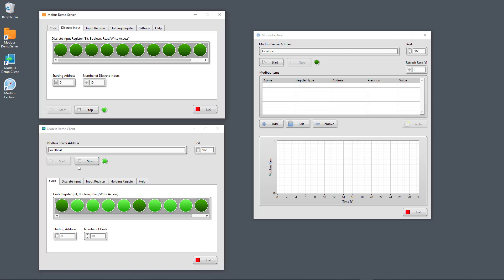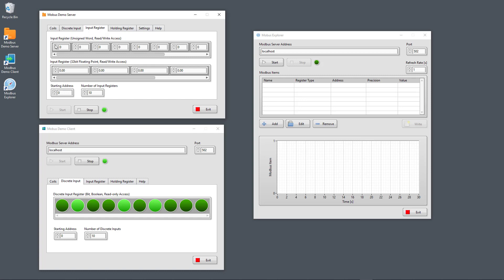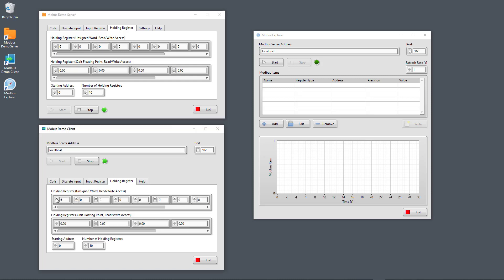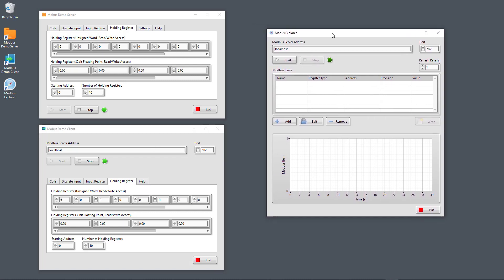I can also change the values on the client and you see the values are updating on the server. Discrete input can only be changed on the server while it is read-only on the client, and the same for the input register — I can change values on the server and read them on the client, but it is read-only on the client. For the holding register, I can change the value on the server but also change it on the client. Modbus Explorer is actually also a Modbus client.